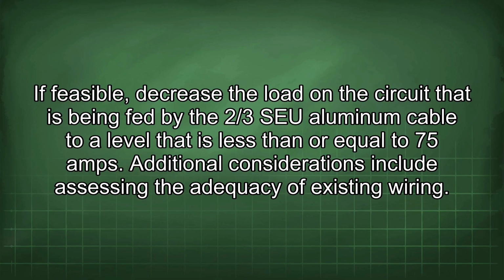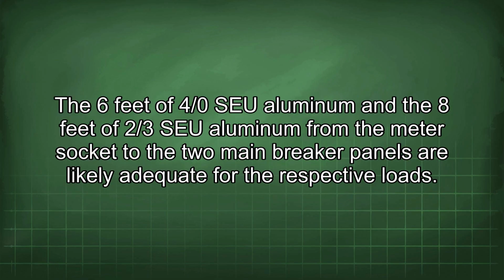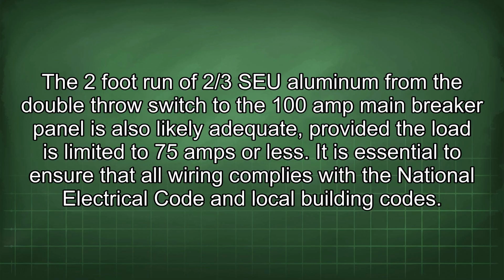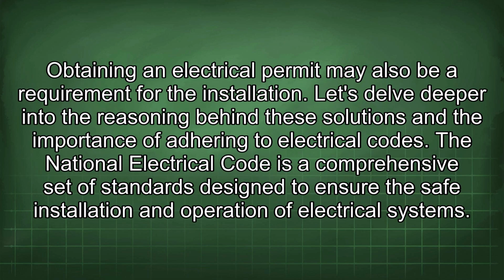Additional considerations include assessing the adequacy of existing wiring. The 6 feet of 4/0 SEU aluminum and the 8 feet of 2/3 SEU aluminum from the meter socket to the two main breaker panels are likely adequate for the respective loads. The 2-foot run of 2/3 SEU aluminum from the double throw switch to the 100 amp main breaker panel is also likely adequate, provided the load is limited to 75 amps or less. It is essential to ensure that all wiring complies with the National Electrical Code and local building codes. Obtaining an electrical permit may also be a requirement for the installation. Let's delve deeper into the reasoning behind these solutions and the importance of adhering to electrical codes.